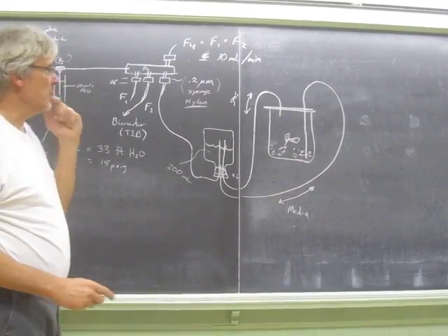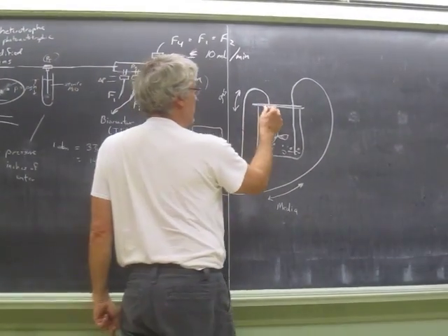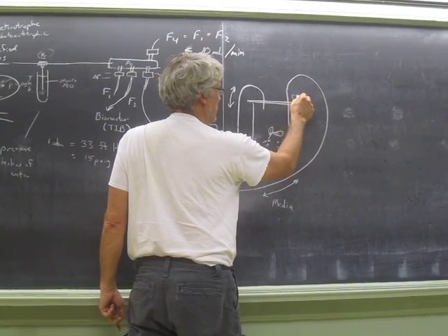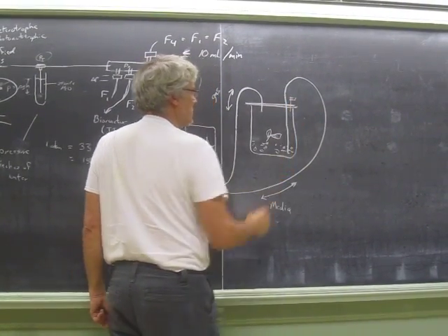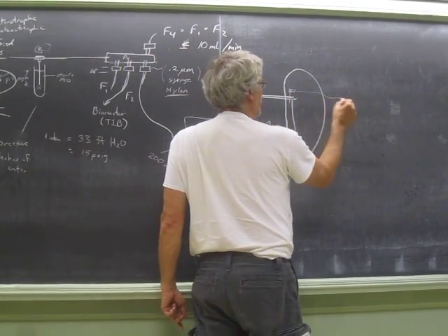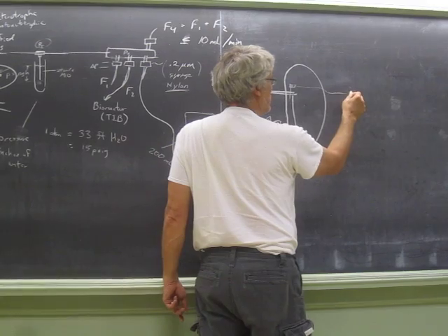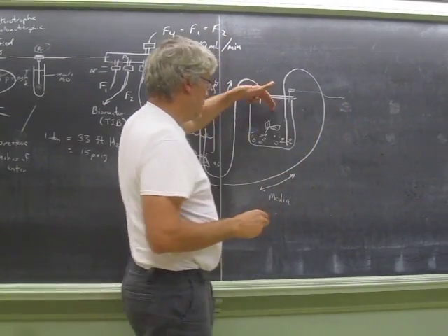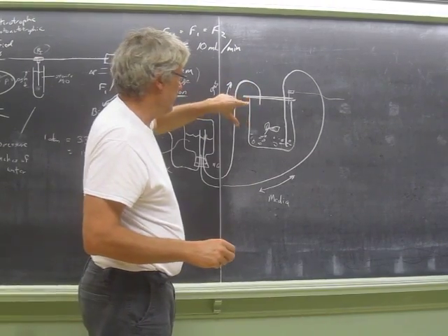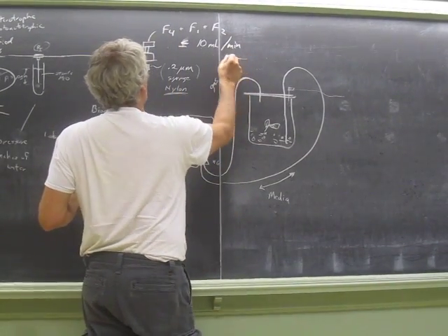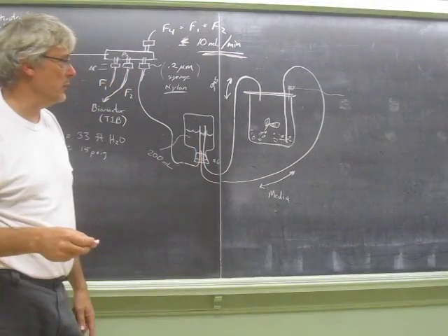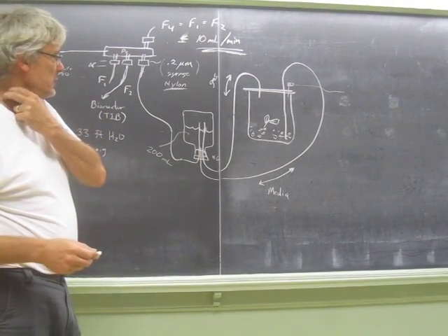And as I had mentioned before, we had actually placed in here pressure transducers. Okay, they were actually relatively inexpensive. But this was just experimental work where we could then interface that to a computer and measure the pressure inside the headspace here. And that's how we did a live diagnosis to decide on which flow rates were necessary in this particular configuration to maintain sterility.